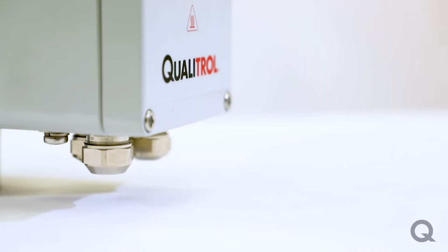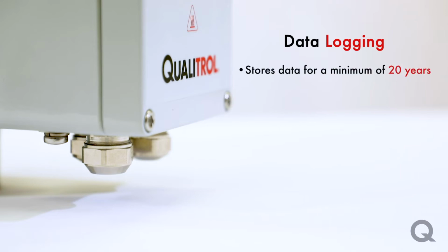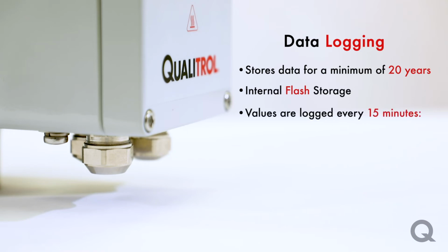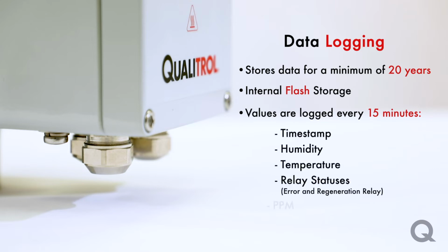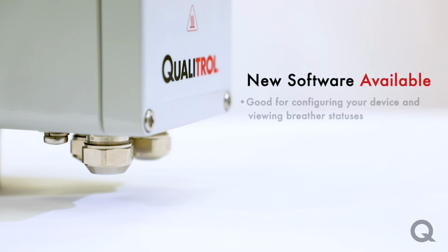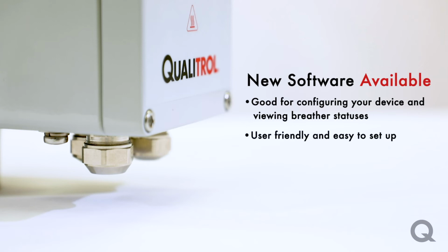In addition to the ppm regeneration threshold, we have also added a new data logging feature to the breather. The data logging feature stores data for a minimum of 20 years and has an internal flash storage. The data logging values will be logged every 15 minutes, and it'll record things like timestamp, humidity, temperature, the relay statuses, and ppm if you have that enabled. We also have a brand new software that you can use to configure the device and view the current status of the breather. It is really user-friendly and makes it easy to set up in the field.